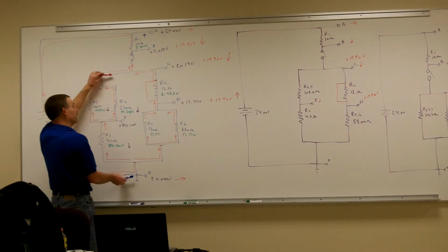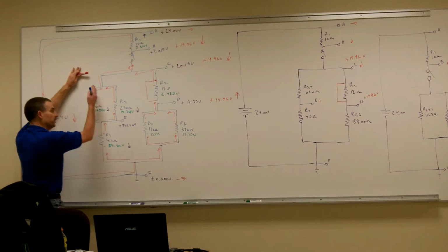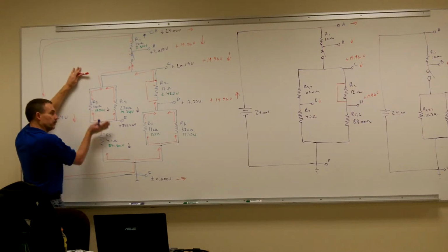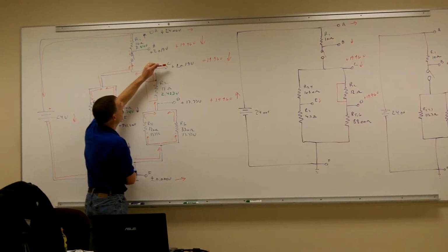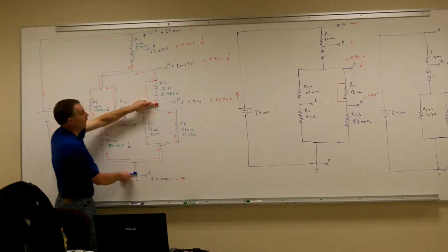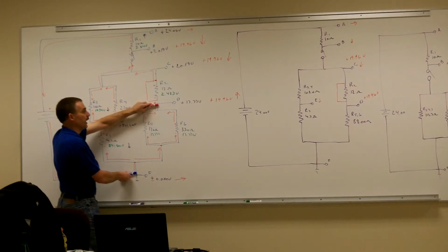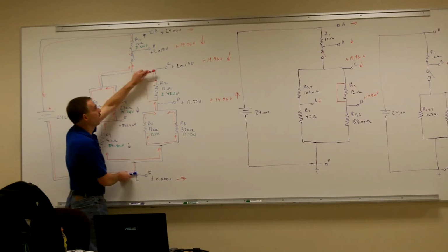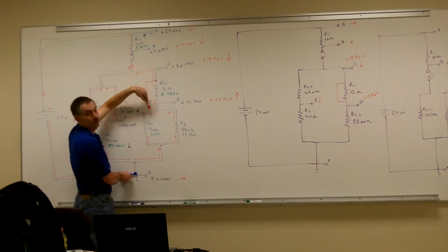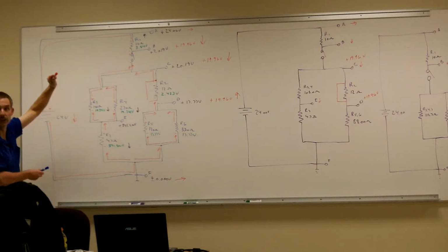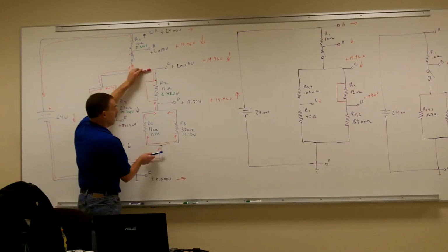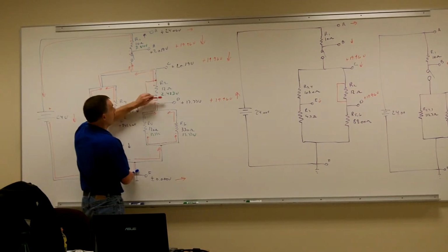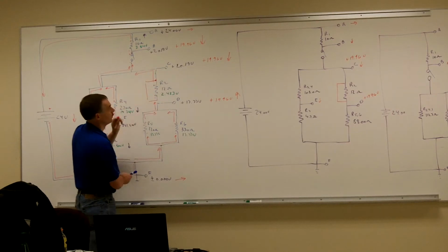So I knew that on this side of the circuit, nothing changed. If there were no changes on this side, I know this circuit is probably good. Then I come back over to this one, and all of a sudden this one dropped, whoop, that one went up. At that point I knew I had probably found the problem somewhere in between these two test points. The minute I saw that change, I knew it was going to be in between those two test points.